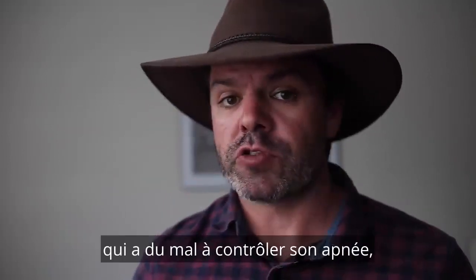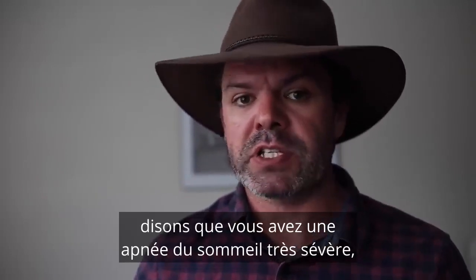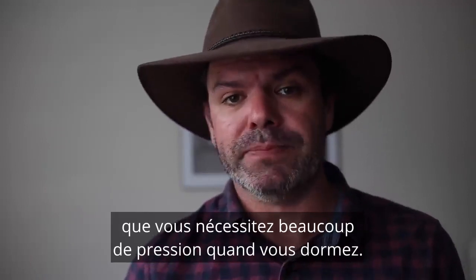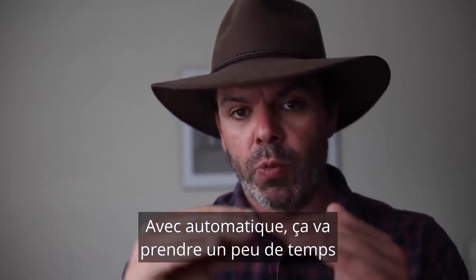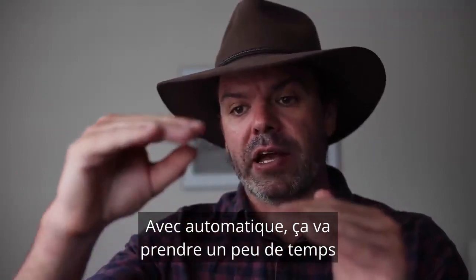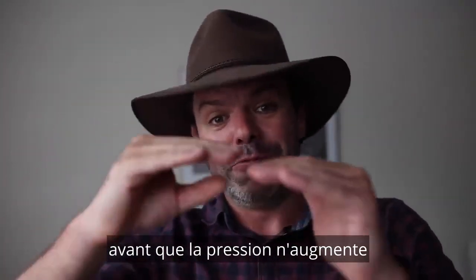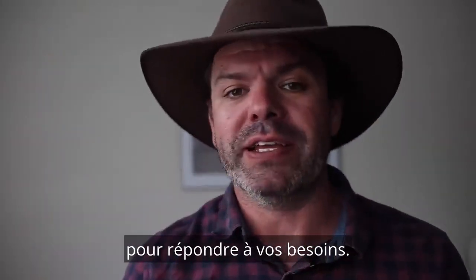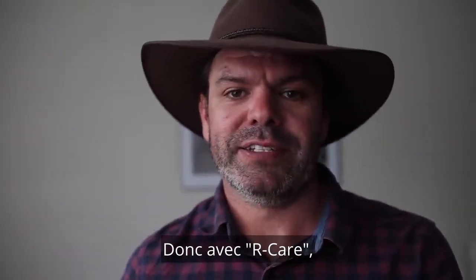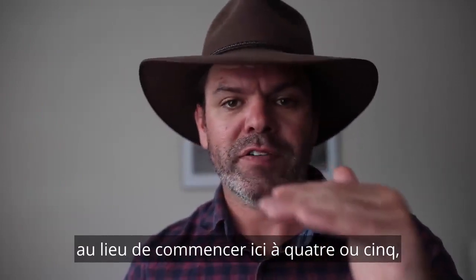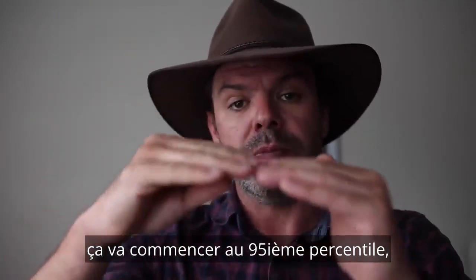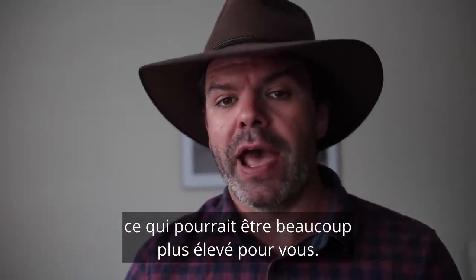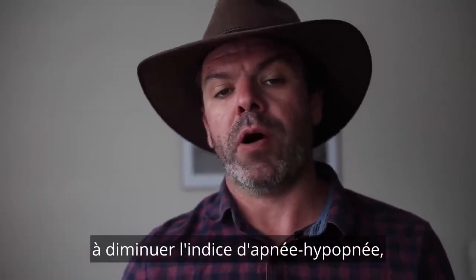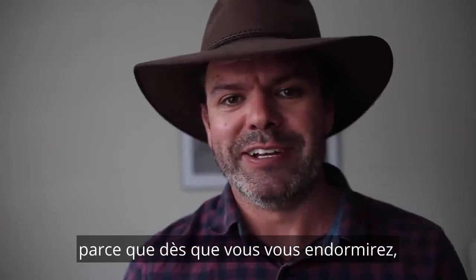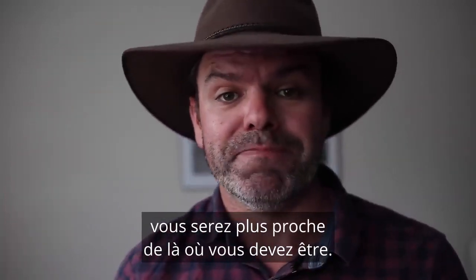Now, if you're someone who's struggling to control your apnea, let's say you've got very severe sleep apnea, and as soon as you fall asleep you need a lot of pressure. With an automatic, it's going to take a bit of time before that pressure ramps up to meet your needs. So with R-Care, instead of starting down at 4 or 5, it's going to start at the 95th percentile, which might be a lot higher for you. It's really going to help lower that apnea hypopnea index, because as soon as you fall asleep, you're going to be much closer to where you need to be. I hope that makes sense, I know it's confusing.